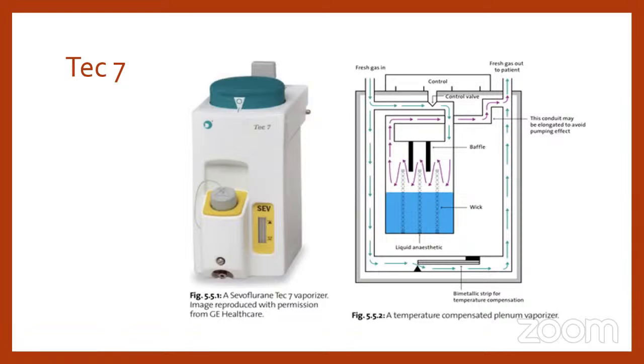There is a release button, an extra safety measure that has been incorporated in this vaporizer, on the back side of the wheel. This is the zero indicator. Exactly opposite to this place, there will be a knob. Only when we push that knob can the vaporizer dial be rotated here and there. So the concentration which comes out of the vaporizer will be regulated. So it is an extra safety measure incorporated in this Tec 7 vaporizer. Without pressing that lock, we cannot rotate the dial. So the wheel present on the vaporizer cannot be turned left or right, and the leakage of liquid anesthetic agent will be less.